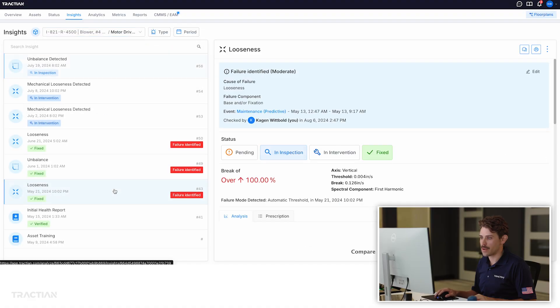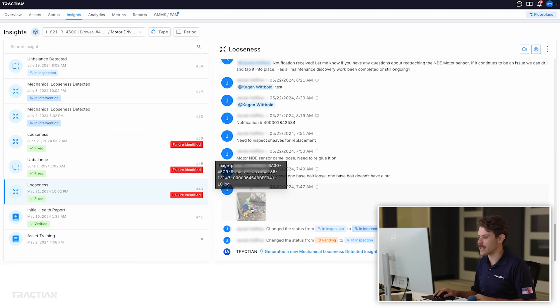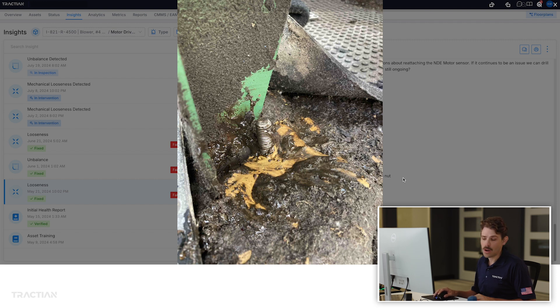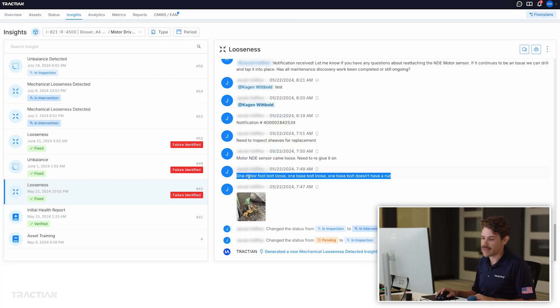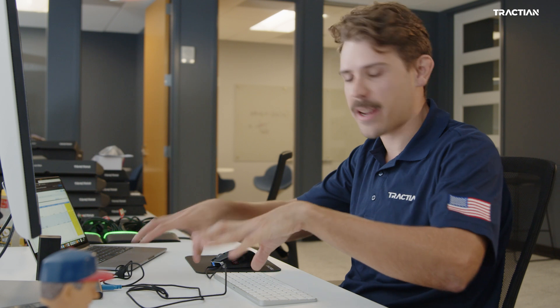He realized there may be a potential issue with the blower and found a looseness problem when he went out to do his inspection. He was able to take a picture of the looseness issue, showing that there was a missing nut off of the motor — an obvious indicator of a looseness problem. He mentioned in the comment field of the insight that he found one motor foot bolt loose, one base bolt loose, and one base bolt with no nut. This is incredibly important because it allows that motor to rock back and forth and exacerbate any potential bearing problems, lubrication problems, and structural issues already ongoing.